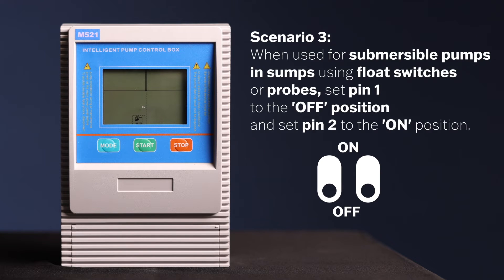Scenario 3: When used for submersible pumps in sumps using float switches or probes, set pin 1 to the OFF position and set pin 2 to the ON position.